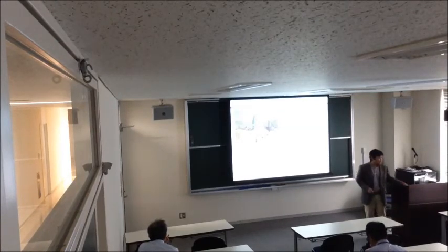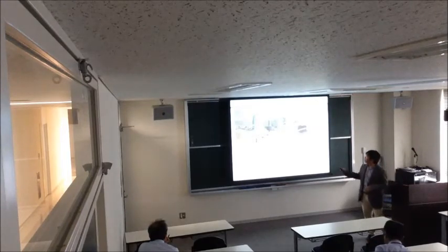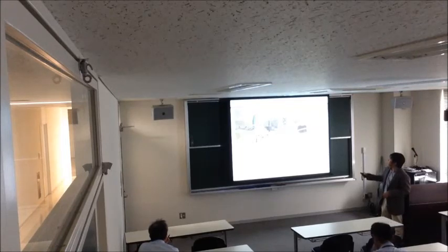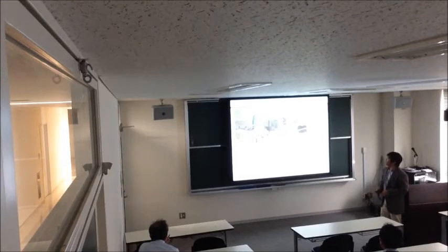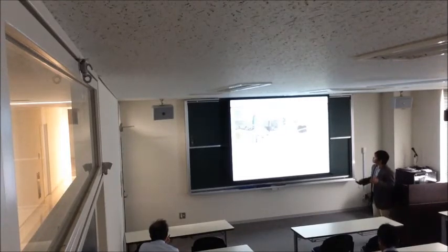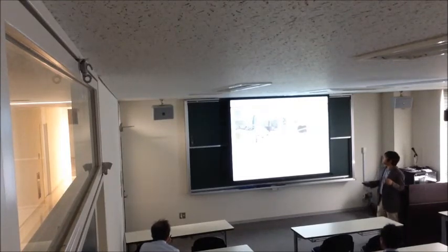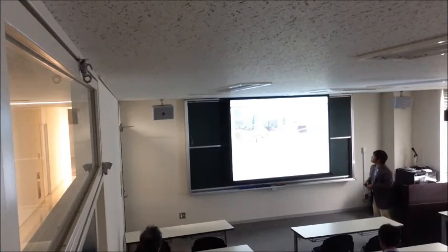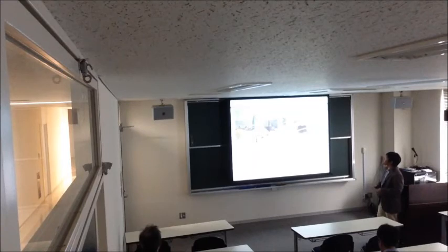And then what happens if the scaling occurs there? You can see that this is the injection pipe, and this is the scaling. This is around 3 months. So every 3 months, the company has to clean this. Of course, this is costly. This is not free. So they have to cut the pipe, I think every 3, 4, 6 meters, and then they clean it mechanically, and it happens continuously in the end.